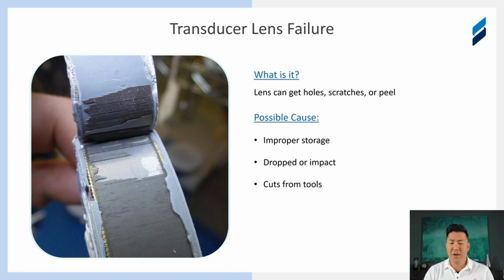From our experience in repairing a lot of transducers, oftentimes it's improper storage. We've seen them in bins where they kind of rock around, and especially during transport, they bang against things that are also in that bin. They're dropped or heavy impact. When they're dropped, the edge between the hard plastic housing and the lens can actually separate a little bit, and you wouldn't see it right away, but then with continued use of gel, the gel, being water-based, will start soaking in there, and it will start to actually break down all of the adhesives that are inside the transducer.